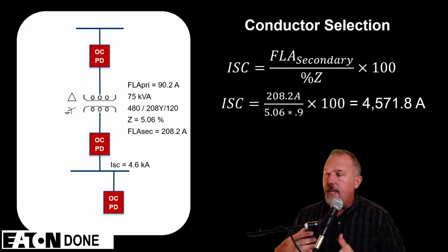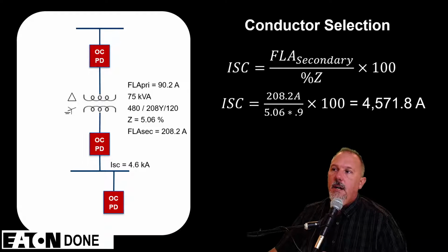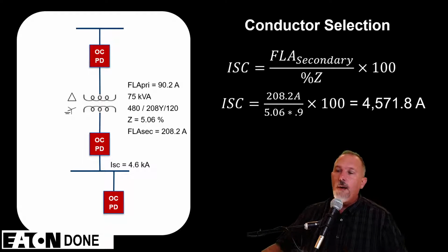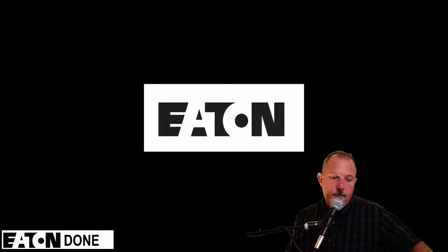In some cases, you might add conductor, or add a source of available fault current on the primary of this transformer that may be less than an infinite bus, which it probably will be. It may impact your secondary available fault current a little bit. I doubt you're going to get down below 2,000 amps, unless you add conductor run. So you could still have an arc flash, a likelihood of an arc flash event.